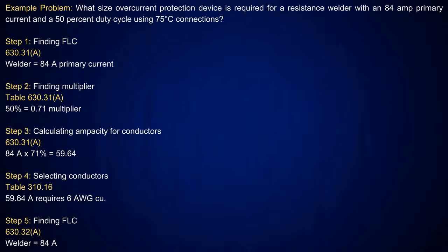I'm going to use the nameplate, which is 84 amps. Now, I'm going to look at this table down here, and I'm going to pick up 50% duty cycle. It's the first one in the table. It's going to tell you it has a multiplier of 0.71. So I'll take the 84 amps at 0.71, gives me 59.64 amps. I look at table 310.16, 75 degree C column. The next size above that, 65 amps, which is a number 6 conductor.